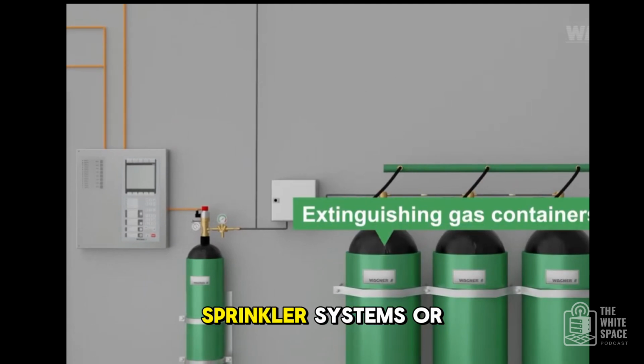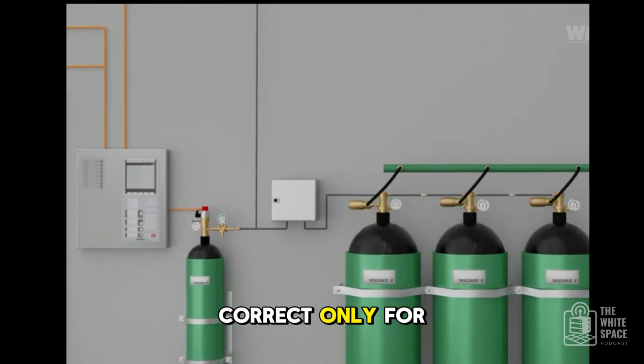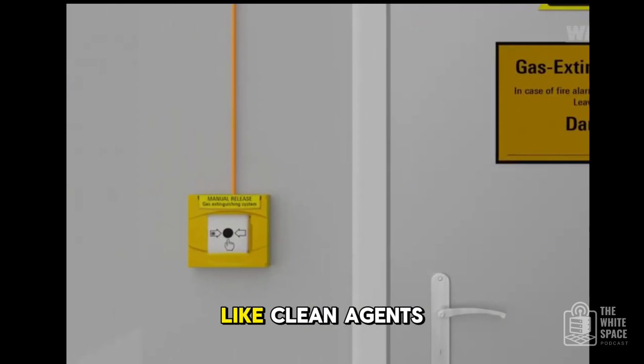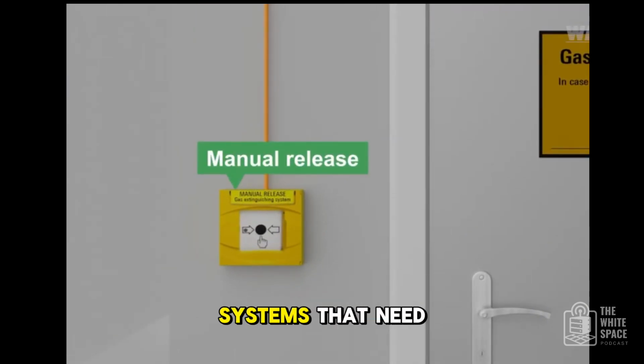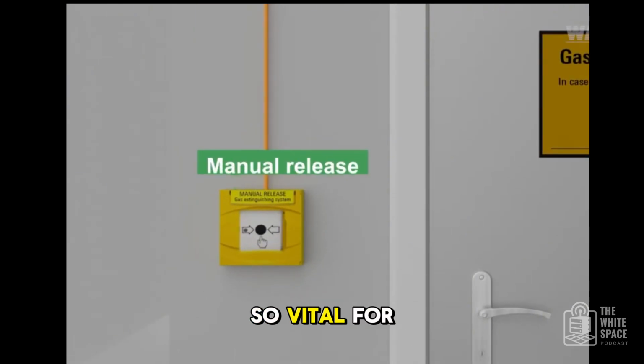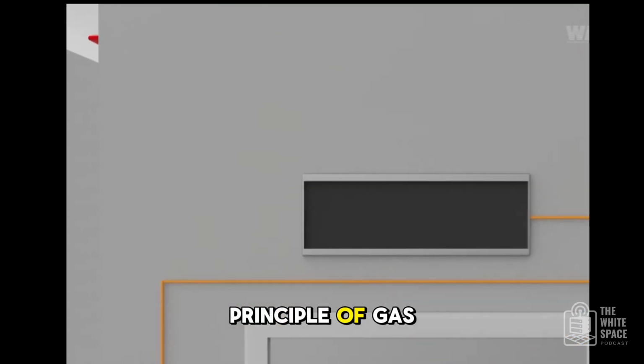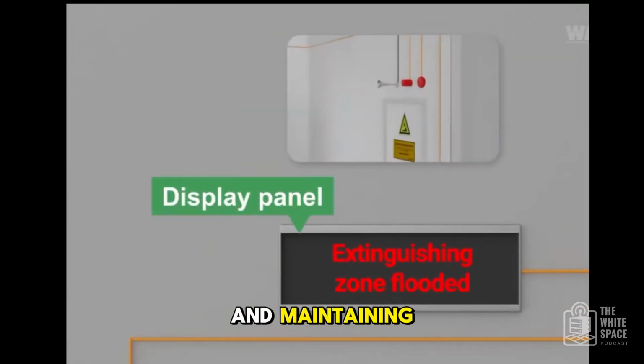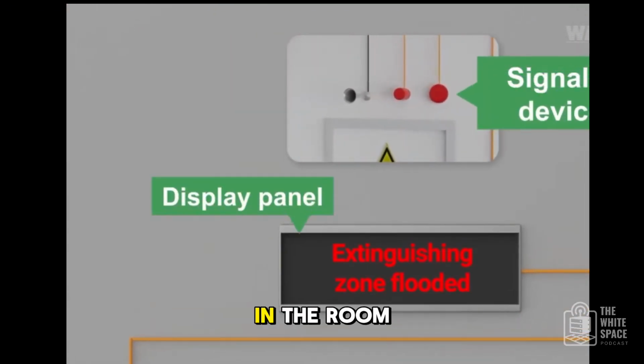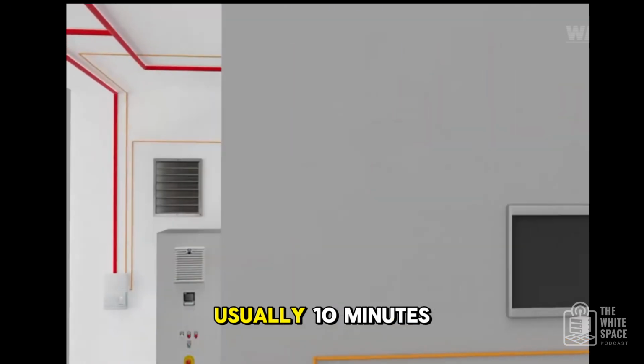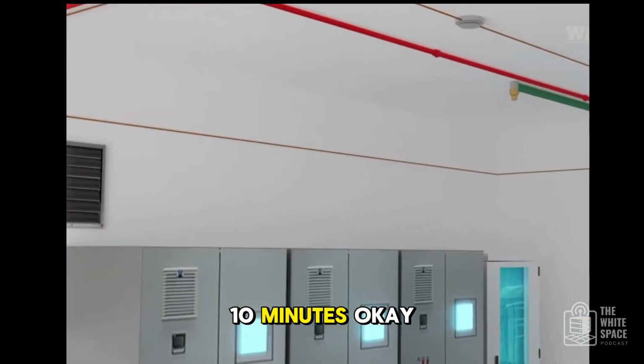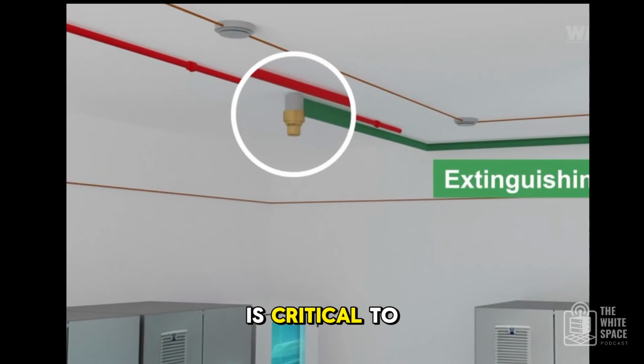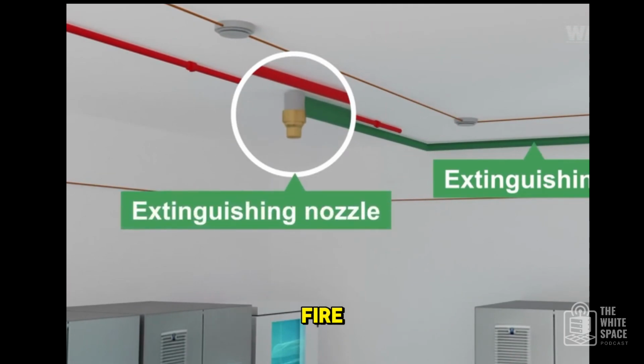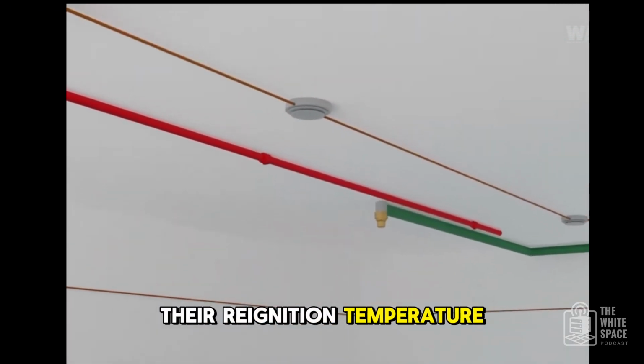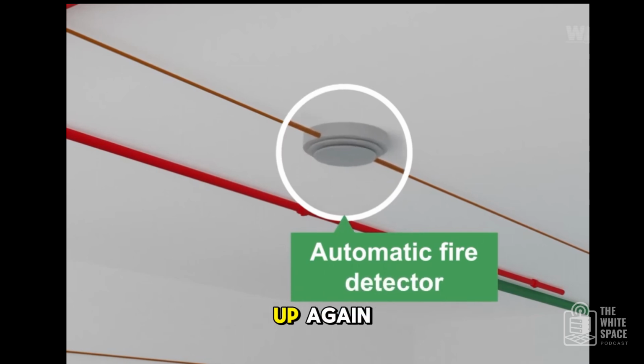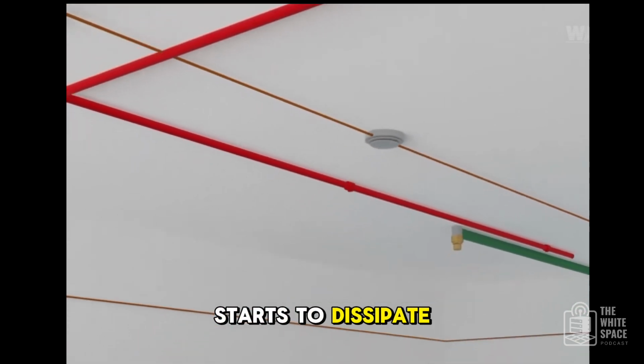Okay, not for sprinkler systems or detection systems. Correct. Only for systems that release a gas agent like clean agents, maybe older CO2 systems that need to flood the entire room. Why is it so vital for those? Because the whole principle of gas suppression relies on achieving and maintaining a specific concentration of that gas in the room for a minimum period, usually 10 minutes. This is called the hold time. 10 minutes, okay. That hold time is critical to fully extinguish the fire, cool materials below their reignition temperature, and prevent the fire from flaring up again once the gas starts to dissipate.